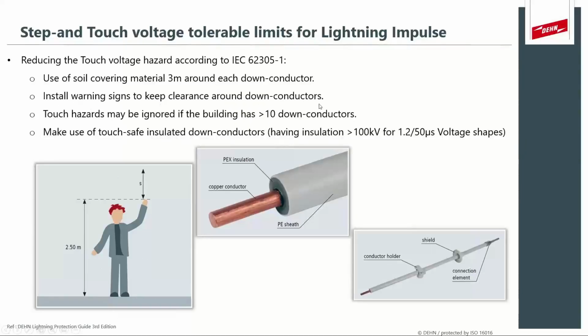Install warning signs so people do not touch down conductors during lightning storms. The standard also says that touch voltage hazards may be ignored if the building has more than 10 down conductors, because the lightning current dispersion through more than 10 down conductors would be so much that each down conductor would not carry sufficient current to actually cause touch voltages.